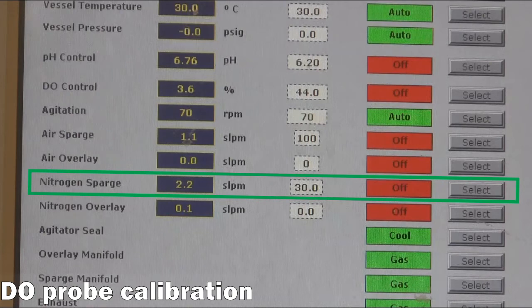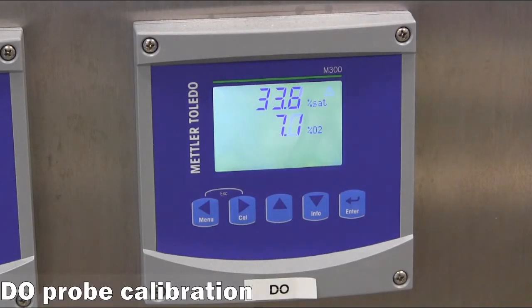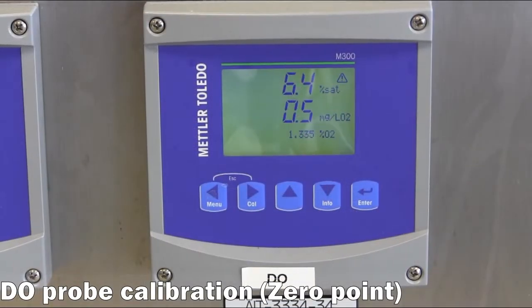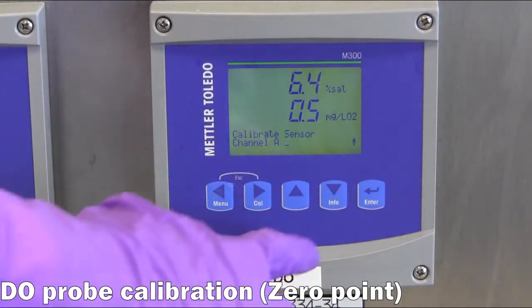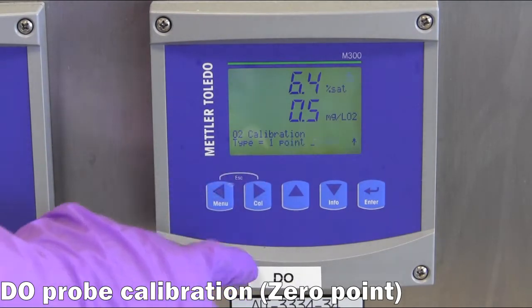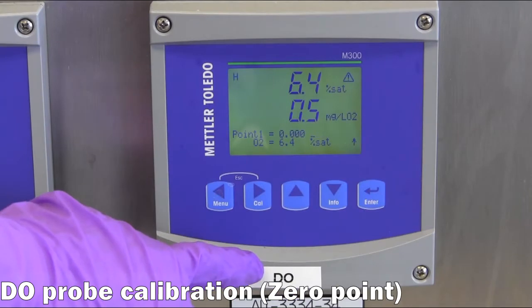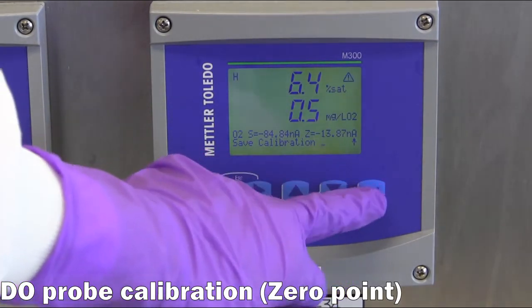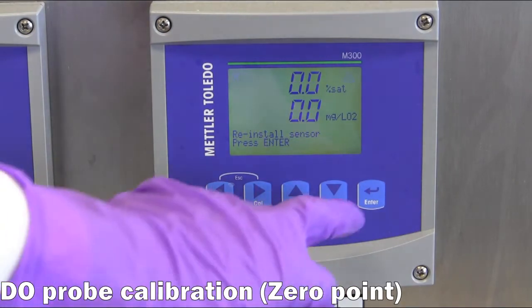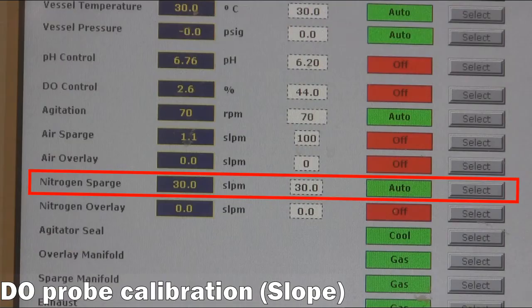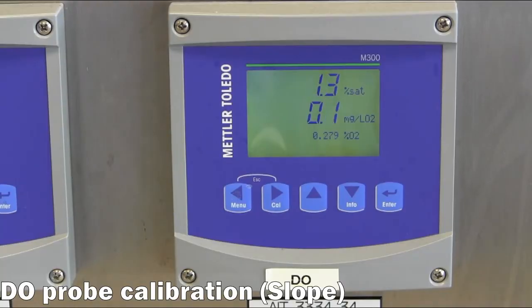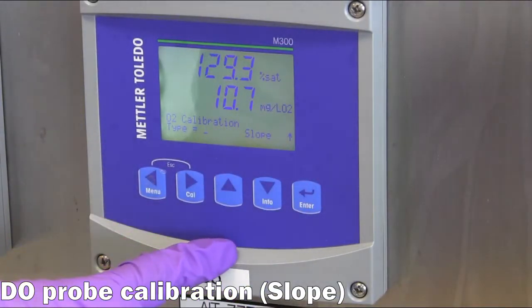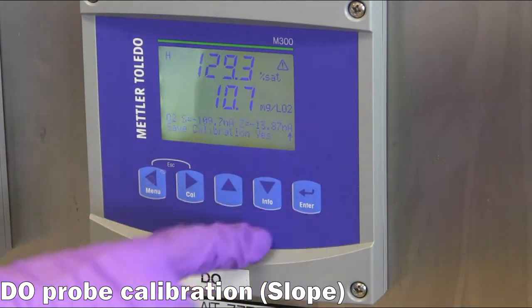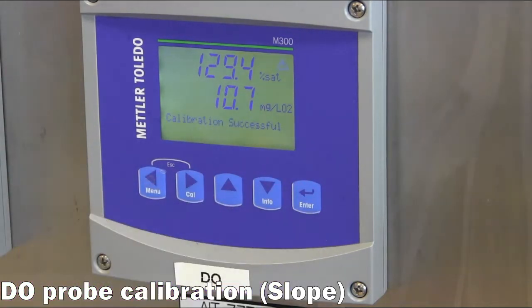DO probe calibration. For the DO probe, turn on the nitrogen sparge and wait until dissolved oxygen levels stabilize. Calibrate 0 point to set the DO reading to 0%. Turn off nitrogen, turn on air sparge, and wait until the liquid is fully saturated with air, indicated by a stable DO reading. Calibrate slope to adjust the reading to 100%. Record and save the calibration. Note that the DO probe calibration should be carried out using the same conditions for temperature, agitation, pressure, and air sparge as for the experiment.